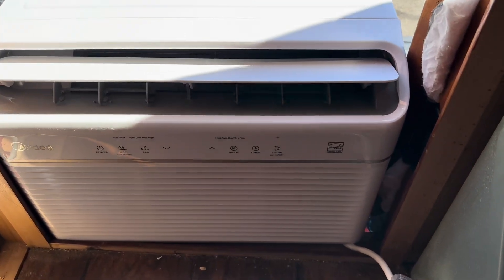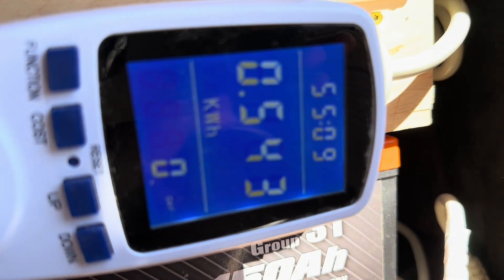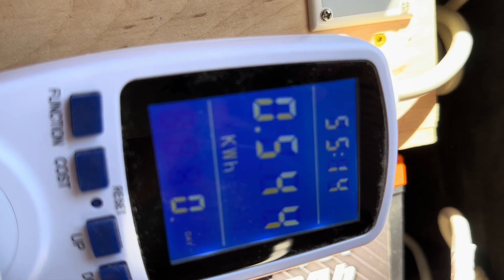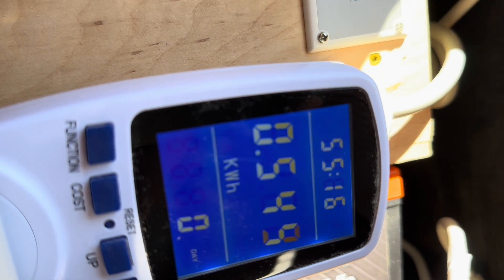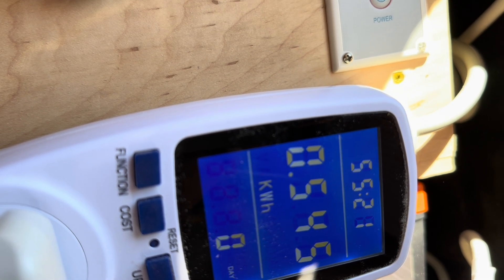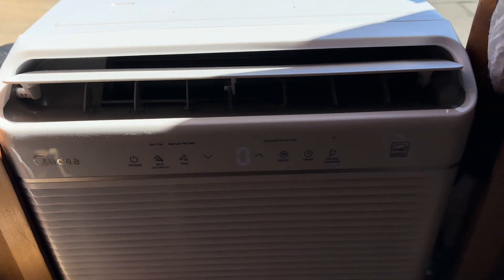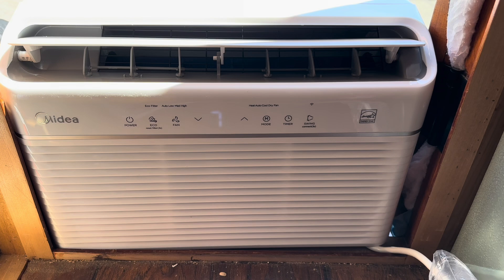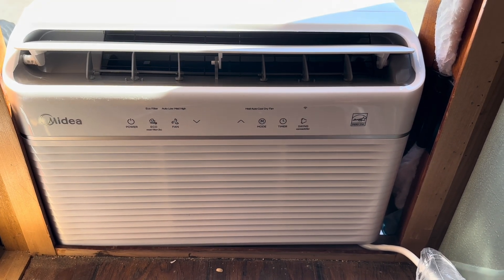Another hour-long test run — actually only 55 minutes, but I'll call it because we're at 0.544 kilowatt hours, which is again much higher than either the other Midea unit or the 5000 BTU AC unit. It's a bit perplexing, but I'm guessing the heat pump unit just is not as efficient as the AC-only unit. Two back-to-back tests with pretty consistent results.